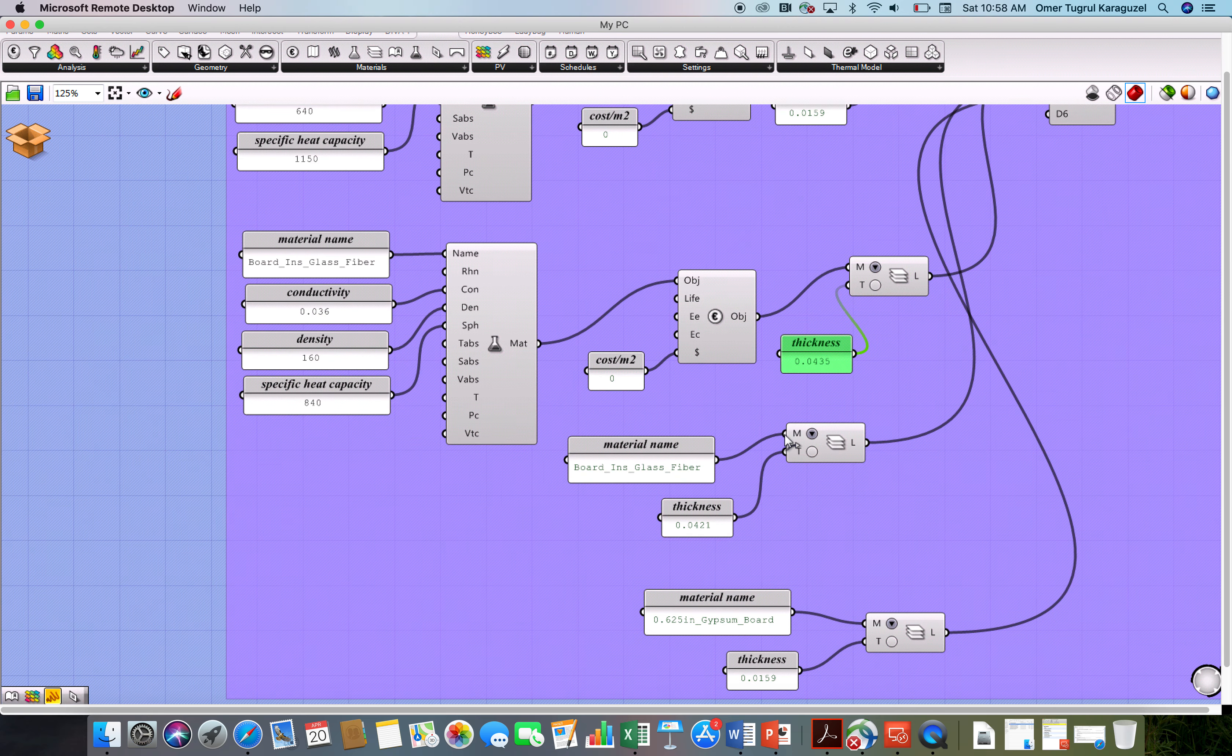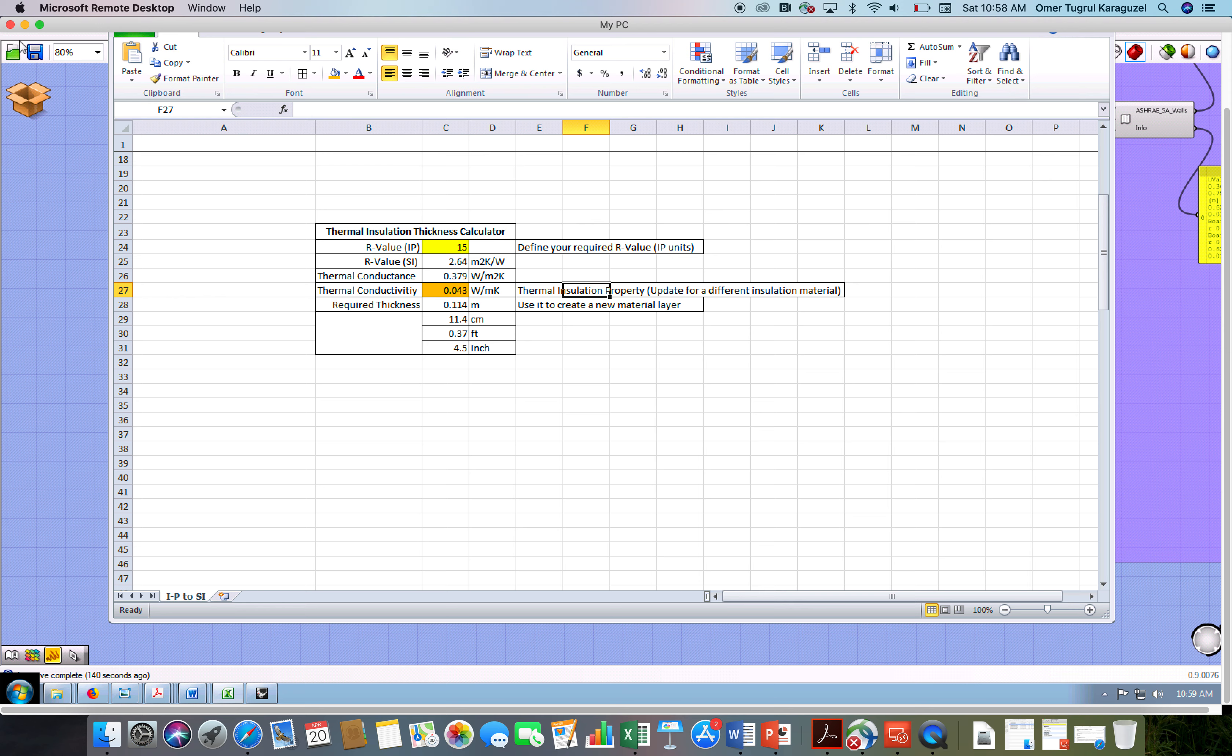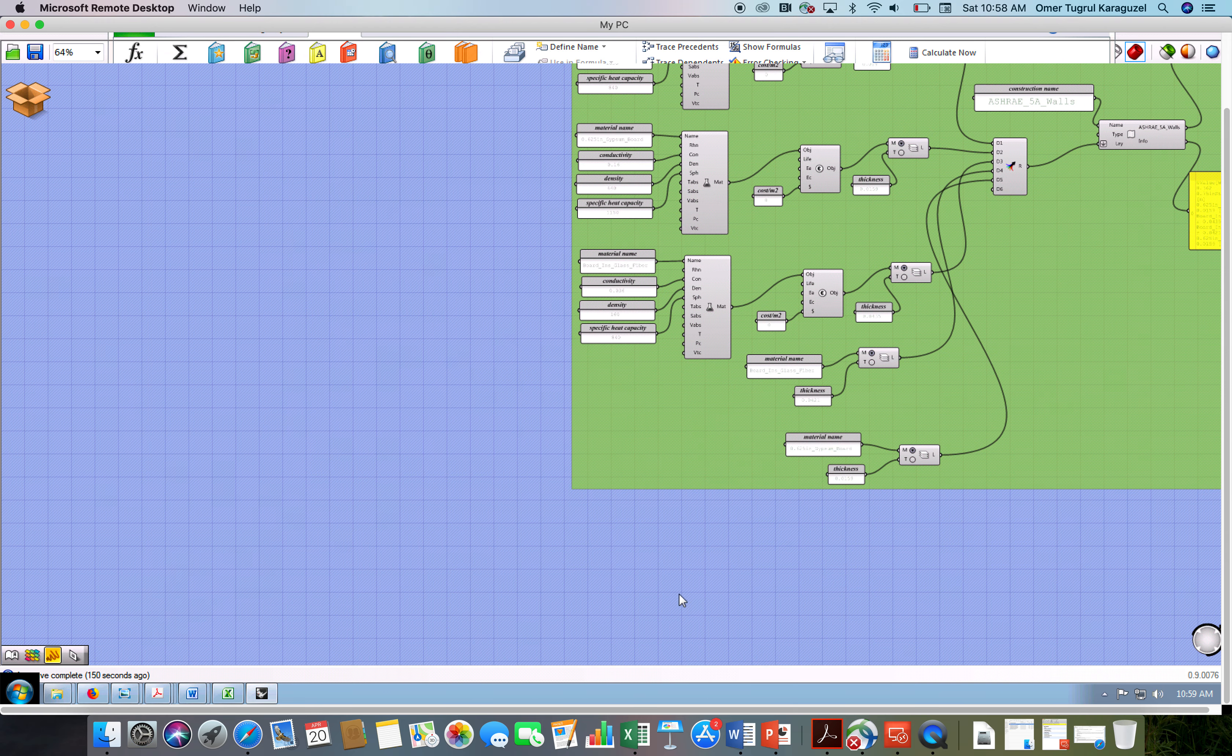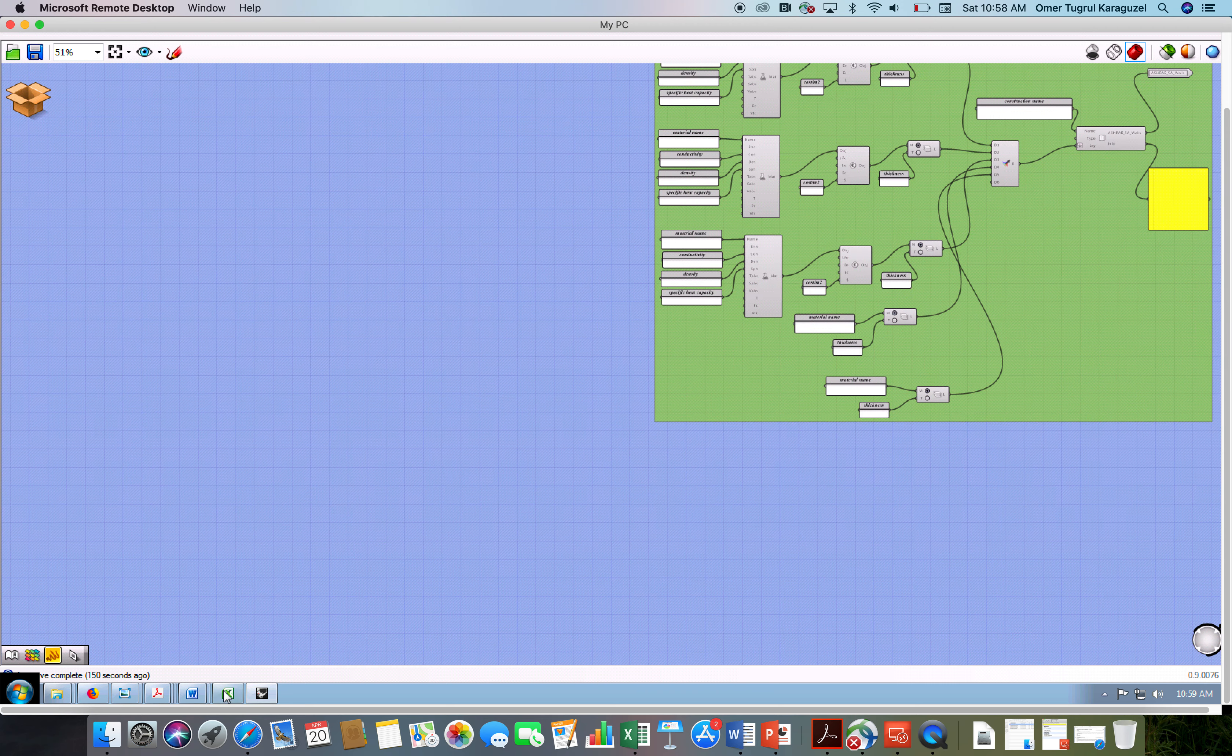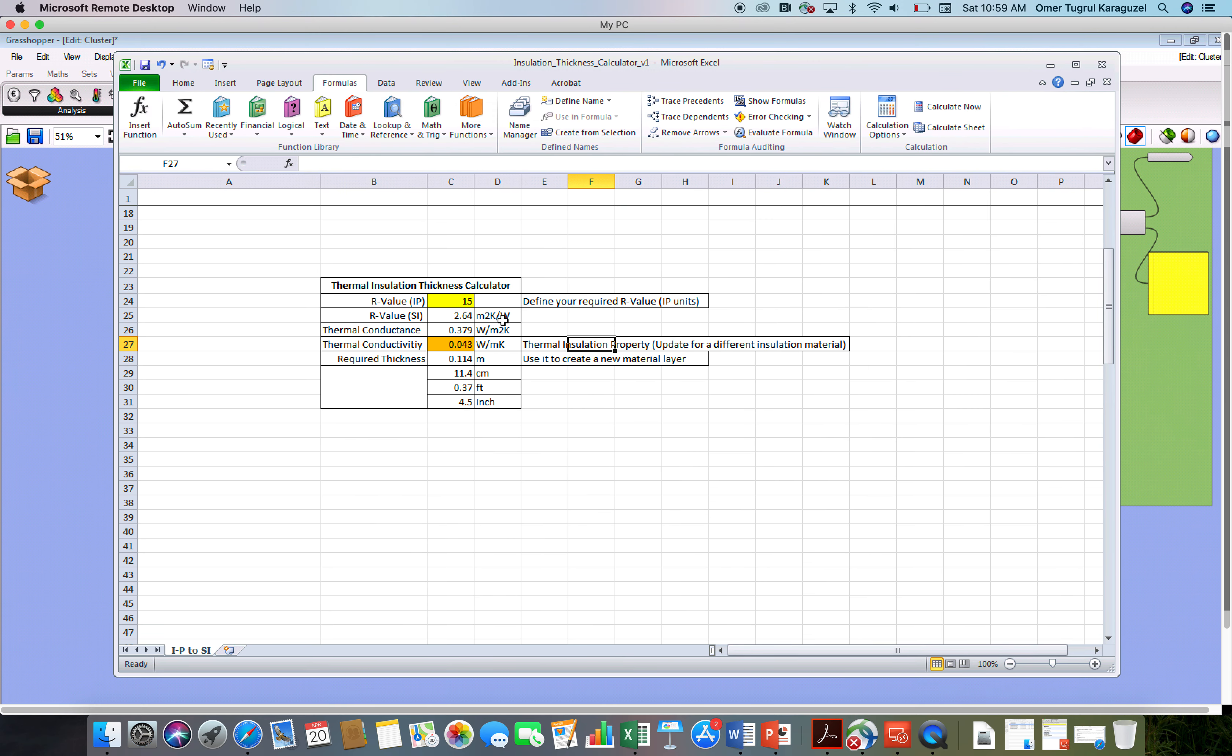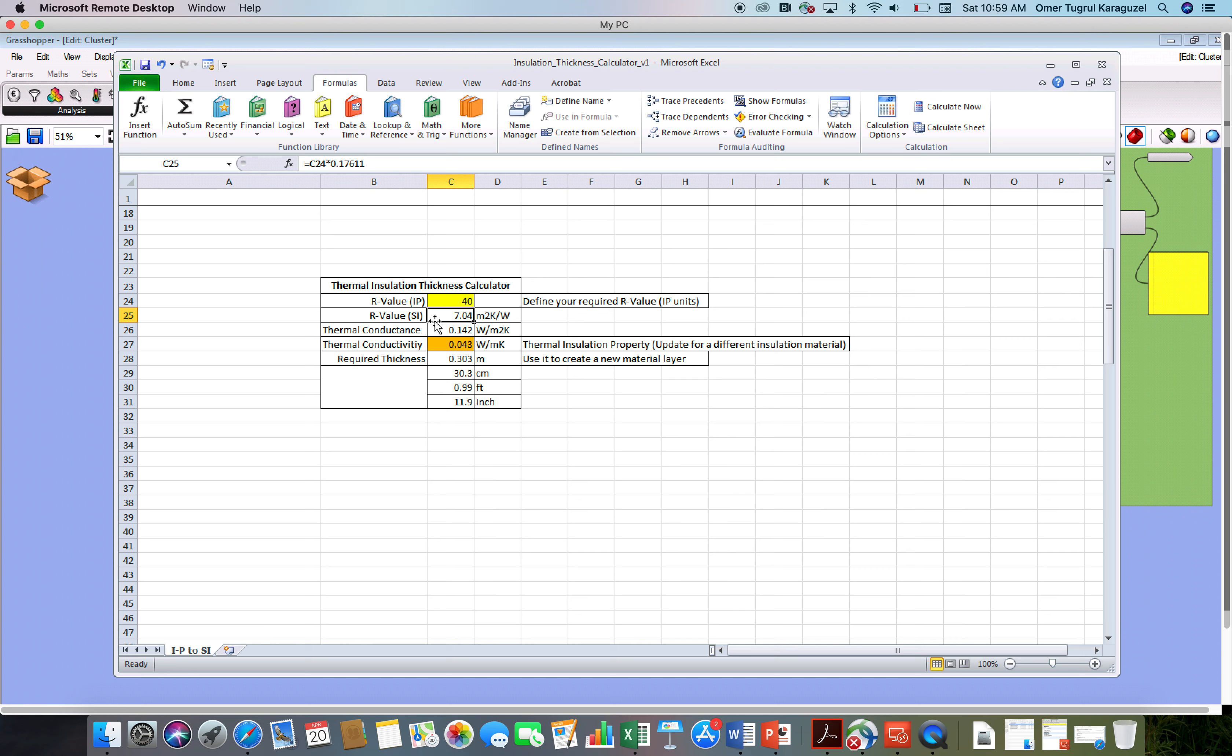To be able to help you guys out, I created a small tool or calculator in an Excel file. Let me show you this. So this Excel file is called thermal insulation thickness calculator. The tool is expecting an R value in IP units from you. So define your required R value in IP units. Say I'm asking for R40. So this immediately converts it to R value in the SI unit metric system, because all the Archsim and all this global algorithm works on SI units in terms of inputs. Outputs, I did some calculations to convert from SI to IP. But as inputs, we need to work with SI units.